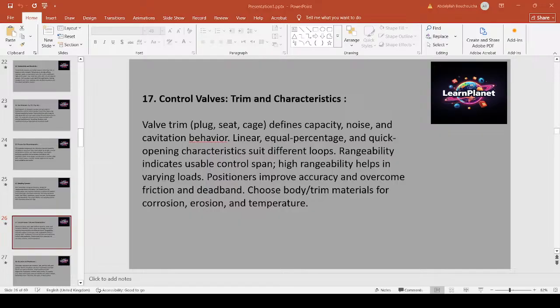Valve trim choice determines capacity, cavitation resistance, noise and controllability. Match valve characteristics to process gain. Equal percent is common for pressure or flow loops with large changes. Rangeability and inherent flow characteristics affect how the valve behaves at low flows. Choose trims and positioners to meet turndown. Select materials to withstand erosion or corrosion and consider anti-cavitation stages where large DP exists. Example: in a high-pressure drop choke feeding a separator, use multi-stage anti-cavitation trim to prevent seat damage.